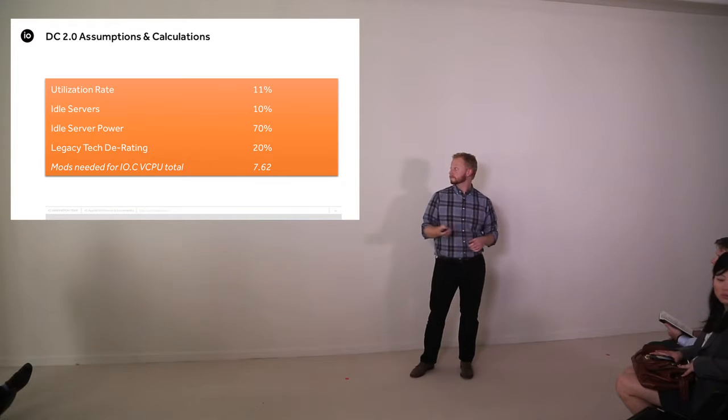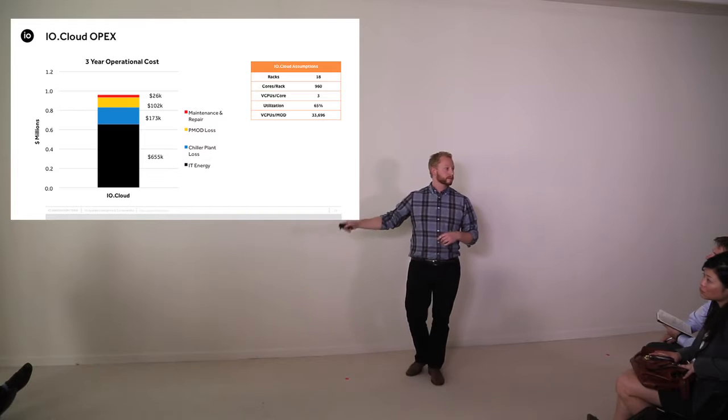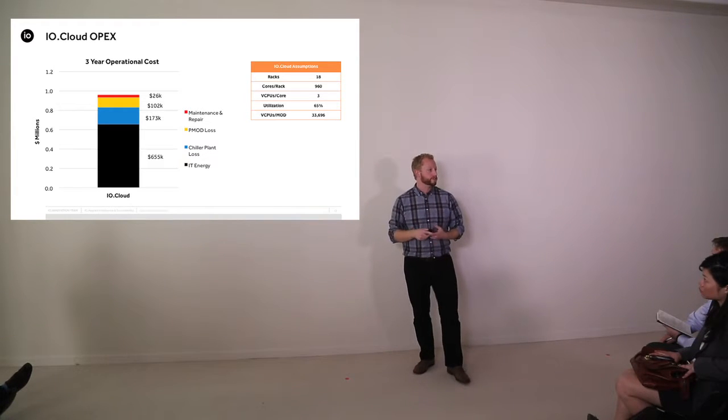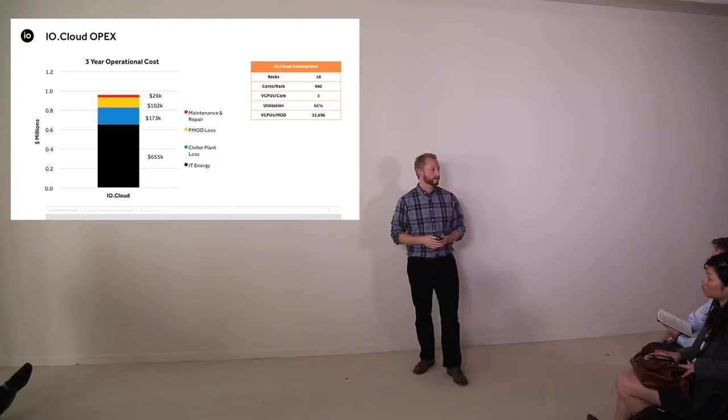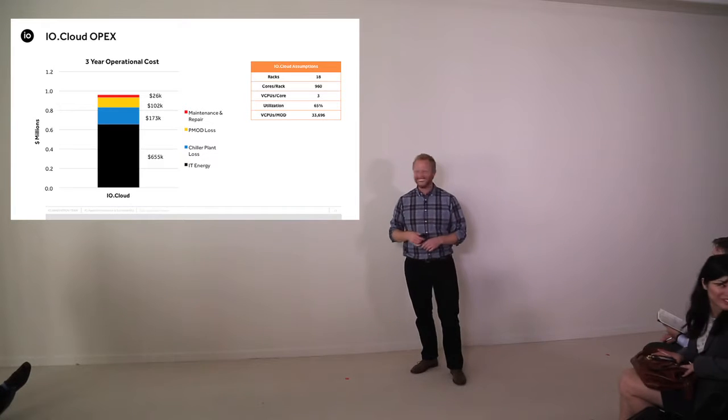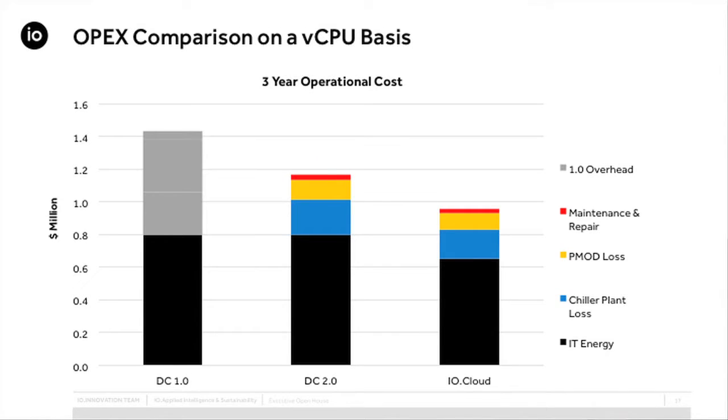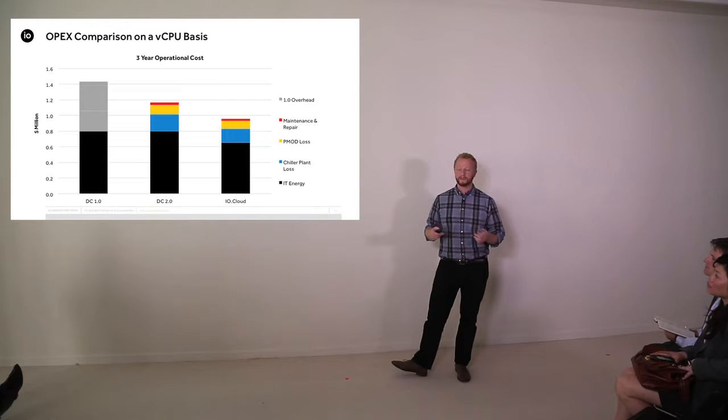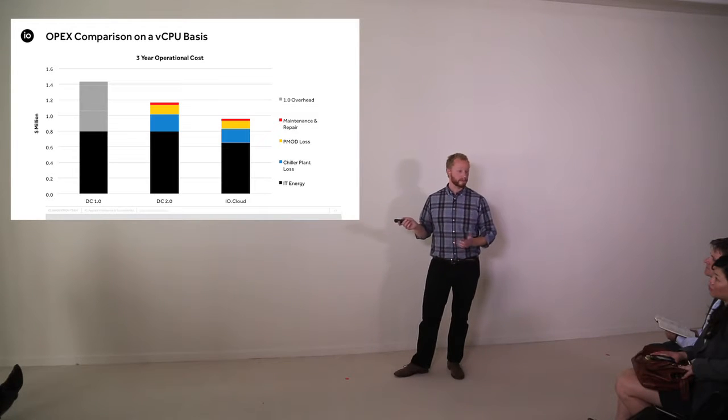So the next step in this model was to figure out how much data center would be needed in a DC 2.0 and a DC 1.0 environment to run the same number of VCPUs. So we found that it would take 7.62 modules to run the same number of VCPUs in a 2.0 environment. This is based off a few assumptions, an 11% utilization rate within the modules, the fact that 10% of servers per rack are idle and that they use about 70% as much energy as a productive server, and also the fact that legacy gear is about 20% less efficient at operating VCPUs than OCP gear is. As you can see, the cost to IT energy jumped from IO Cloud to 2.0 since OCP gear is much more efficient than legacy gear. And for DC 1.0, we assume the same IT energy use and density as in 2.0, but with a higher PUE, 1.73 compared to 1.41. So that's why there's the higher 1.0 overhead cost.